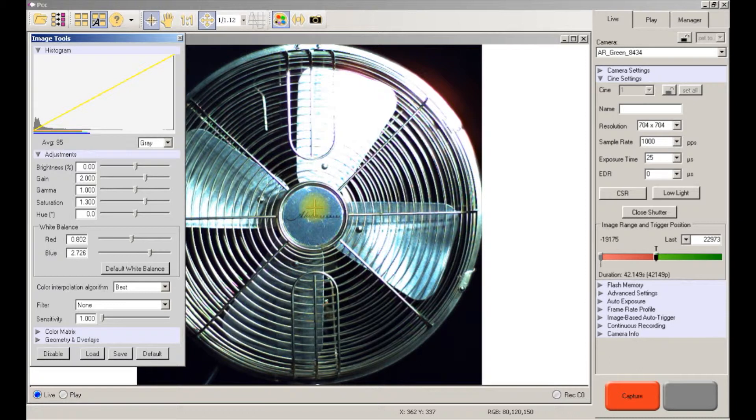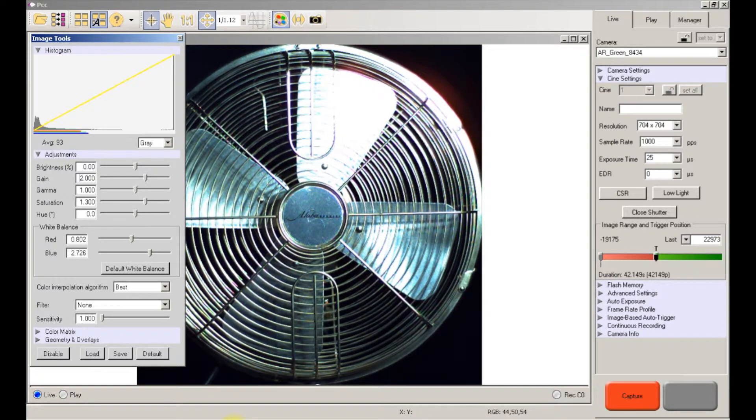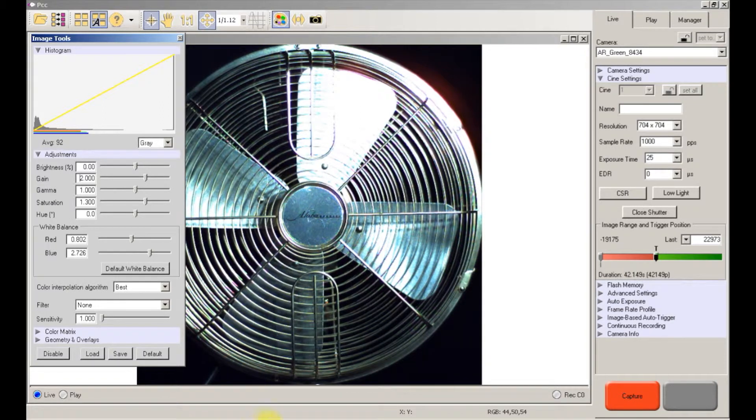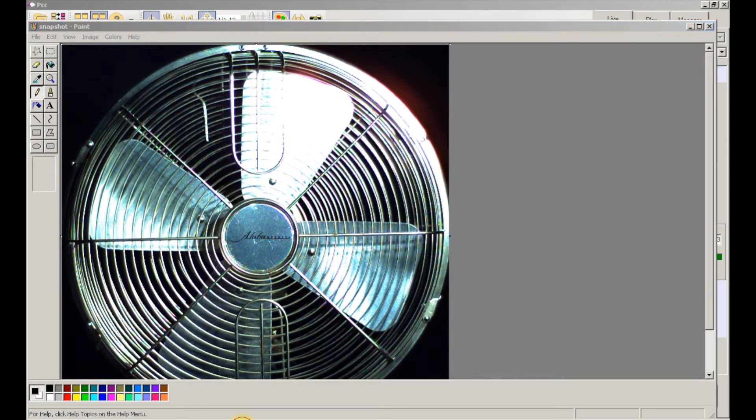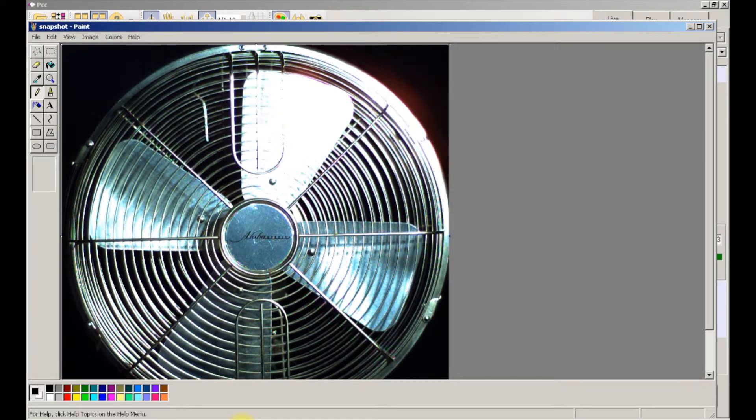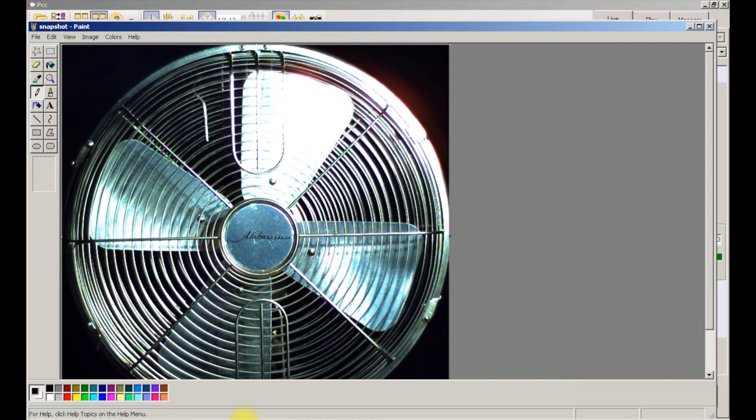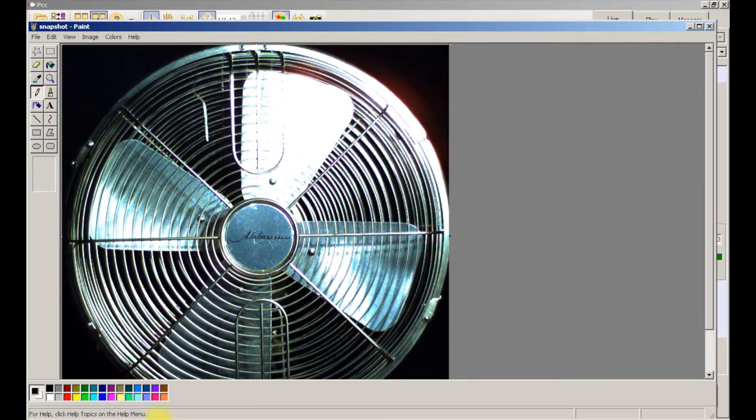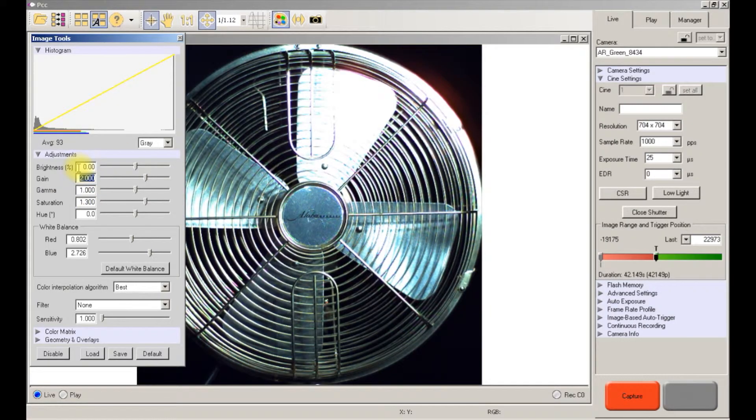This is equivalent to what it was at 50 microsecond exposure. So here's a snapshot of the current settings and here's a snapshot of the 50 microsecond at a gain of one. These two images back and forth here, they're exactly the same. Now we're going to go back into the software, now this time we're going to change the gain back to one.